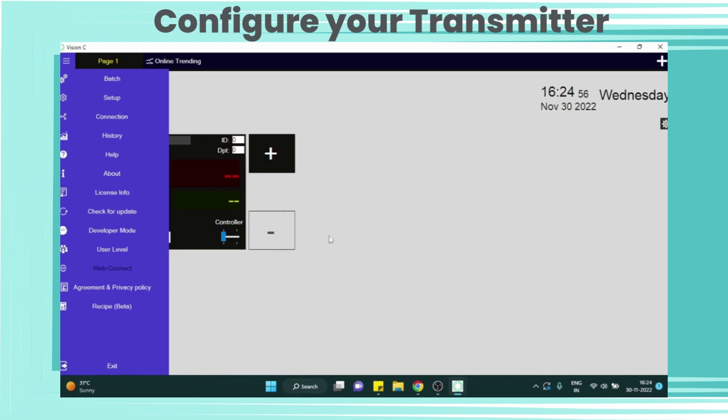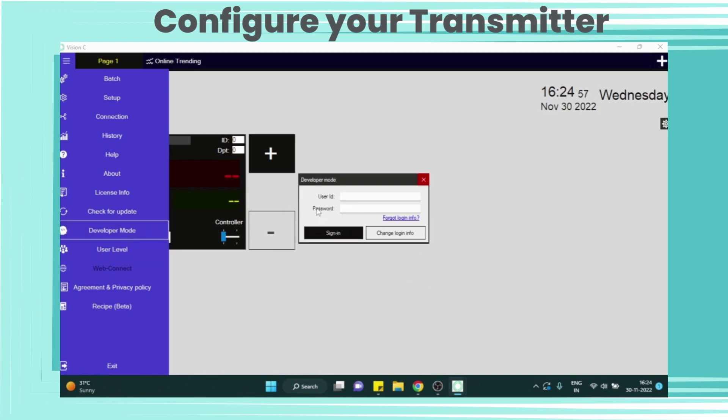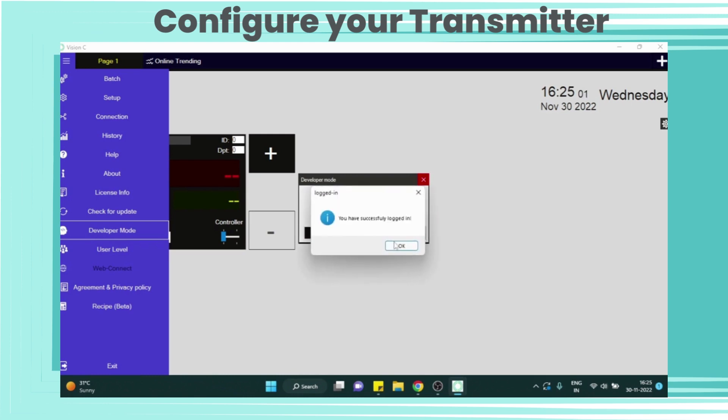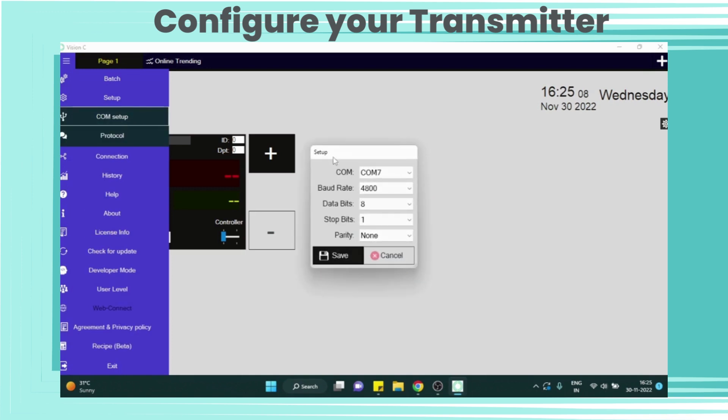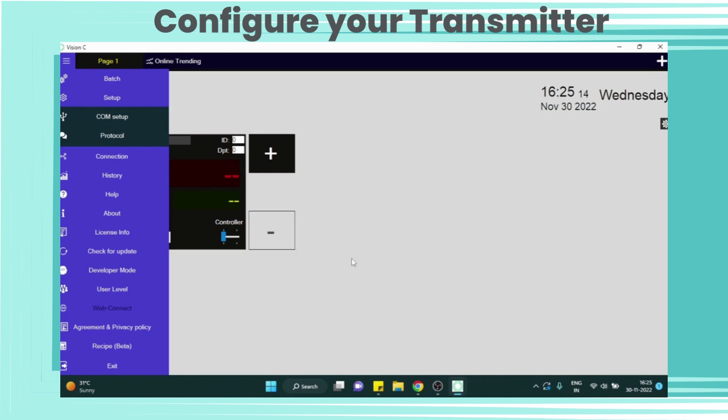Now go to development mode and set the user ID and password. Now go to setup section and do settings for COM parameters. Here we have selected COM 7, baud rate is 4800, data bits is 8, stop bits is 1, and parity is none.